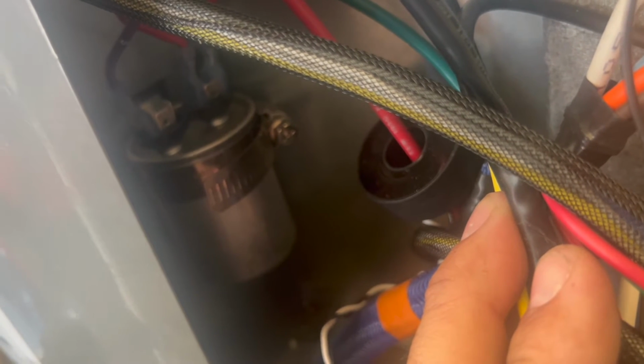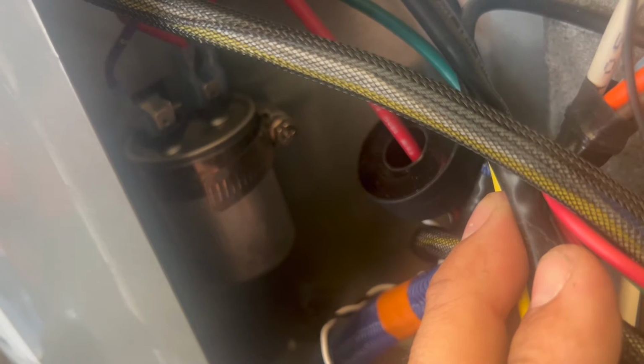Hidden back over here is your capacitor. We want to test that. Different water heaters have different ranges. I think the range on this one's about 330 to 370-ish, plus or minus 10%. Water heater needs to be going, compressor and fan, to get a test on that. And while we're here, we'll go ahead and test these 2 components and see what they say.